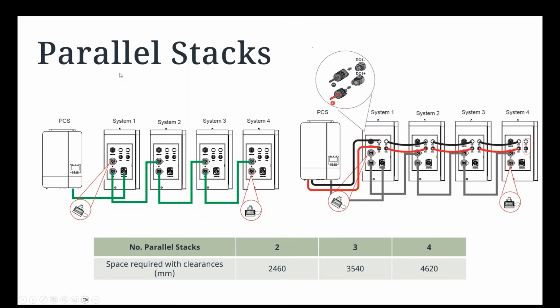Next, let's look at the parallel stack and parallel setup. Pretty simple, as explained earlier. If you have a multi-tower setup with the PCS, your GEN24 Plus for example, data cable wise you'd go from the GEN24 into the inverter terminal. Make sure you have the termination plugs connected to the in port of the first battery and always to the out port of the last battery. Other than that, it's just daisy chaining from out to in, from out to in, and so on.